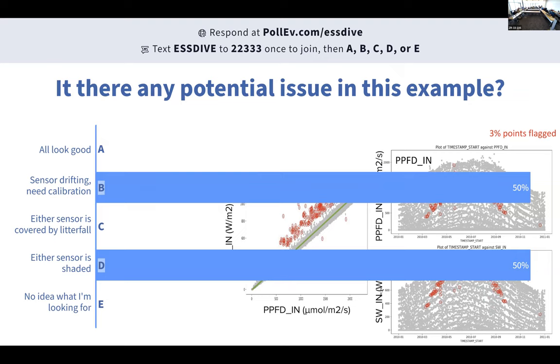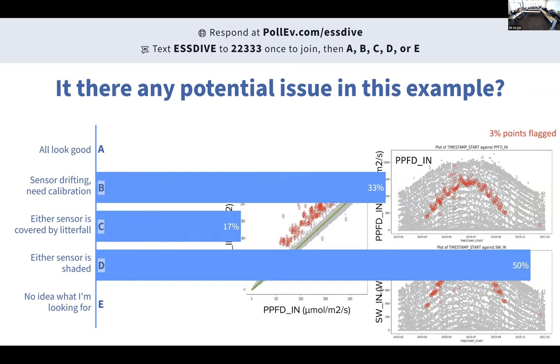For this case, this is one of the sensors being shaded. We see this a lot in the data. Because one of them is being shaded, this only happened during a certain period of time of the day and through the season. So this is one thing we check. It's not sensor drifting. If you have sensor drifting, you're seeing something more consistent across the time, not just periodically.